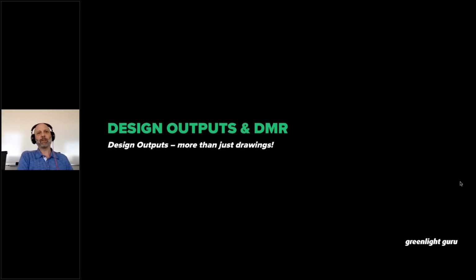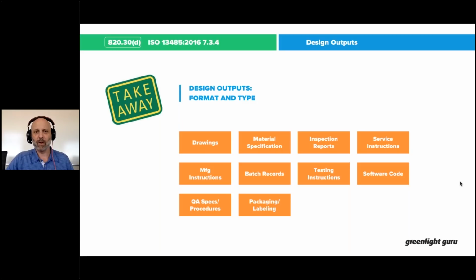All right, moving on. We talked about a moment ago where inputs are like requirements, the what, and outputs are like specifications or the how. So let's talk about design outputs, and let me make the relationship between design outputs and your device master record as well. So again, design outputs are like specifications. They're like the how. And it can include a lot of stuff, things like drawings and specifications, material specifications, manufacturing instructions, packaging, labeling, inspection, so on and so forth.